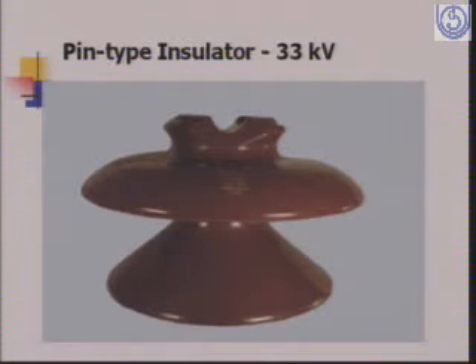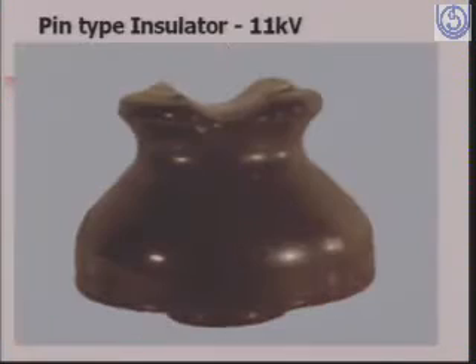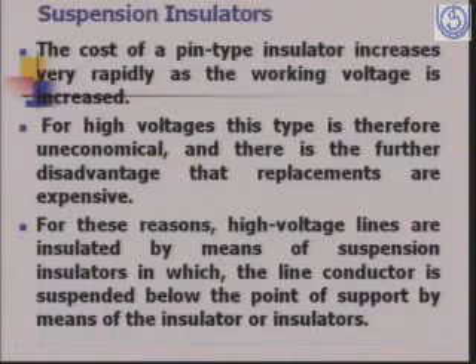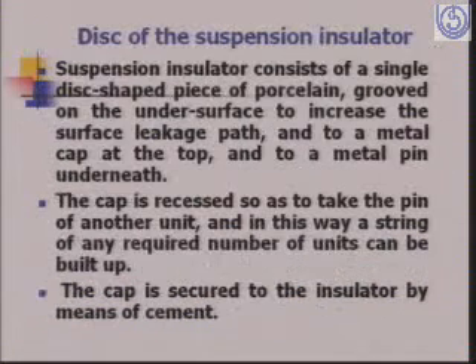This is the example of a pin insulator for 33 kV. This is a pin type insulator for 11 kV. Then we have the suspension insulators. The cost of a pin insulator increases very rapidly as the working voltage is increased. For higher voltages, this type is uneconomical, and there is further disadvantage that replacements are expensive. For these reasons, high voltage lines are insulated by means of suspension insulators, in which the line conductor is suspended below the point of support by means of the insulator or insulators.